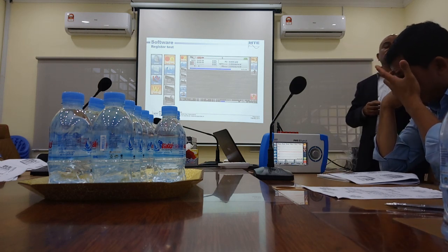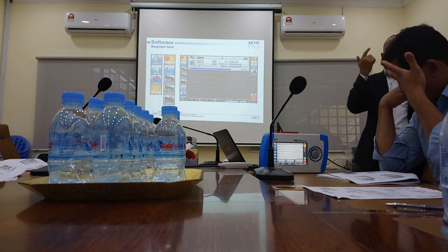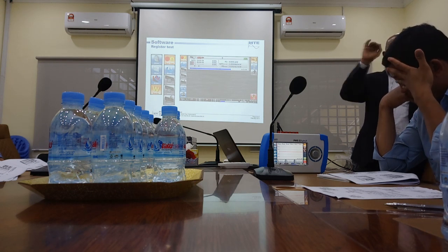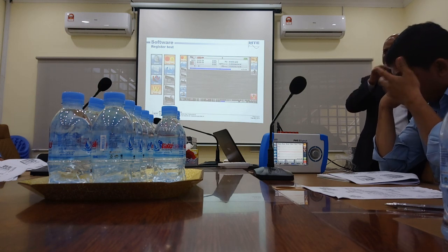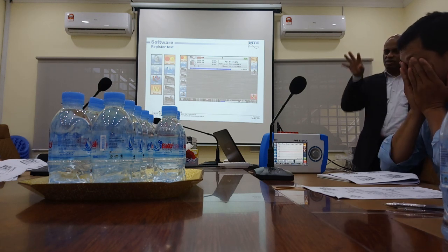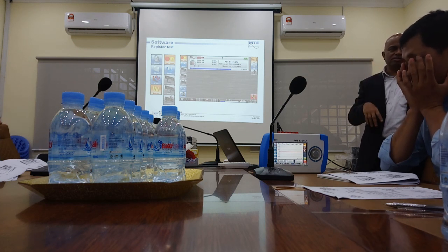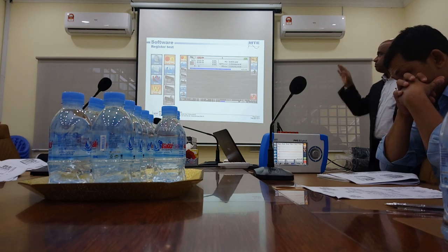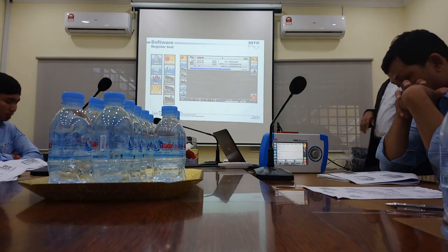So this is also very important sometimes, when the pulsing doesn't work. Like a rotating meter, it is very common, because so much dust or spider web, all sorts of dirt, mud, everything is there, the sensor cannot detect. Or maybe the meter is so old, the marking is gone. So at such times you sometimes need to do manual reading, and tell the error.